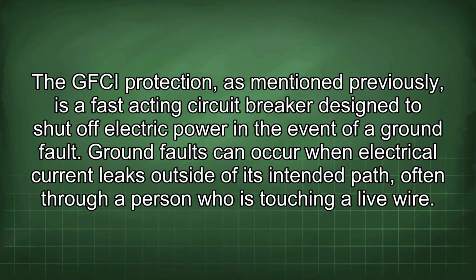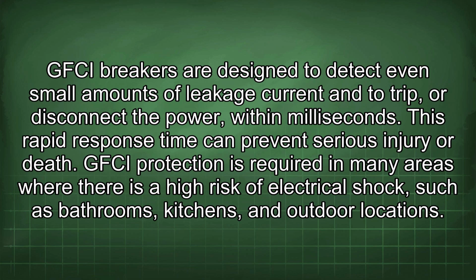The GFCI protection, as mentioned previously, is a fast-acting circuit breaker designed to shut off electric power in the event of a ground fault. Ground faults can occur when electrical current leaks outside of its intended path, often through a person who is touching a live wire. GFCI breakers are designed to detect even small amounts of leakage current and to trip or disconnect the power within milliseconds. This rapid response time can prevent serious injury or death.